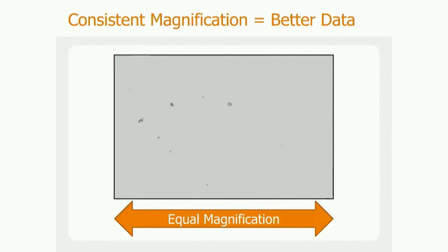So how that applies to MFI is MFI uses an equal depth of field throughout the depth of the flow cell. What that means is that when compared with a narrow depth of field, this provides for much better imaging of all the particles in solution and better accuracy and precision in measuring all the particles in the sample.